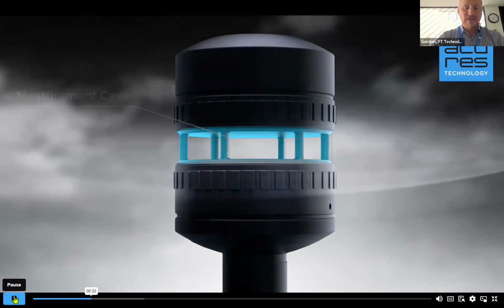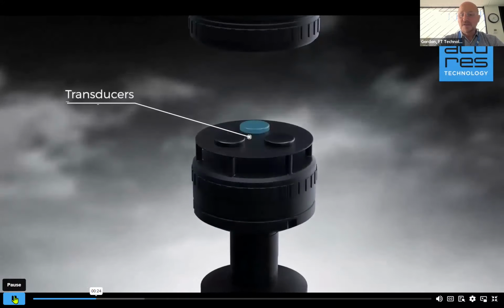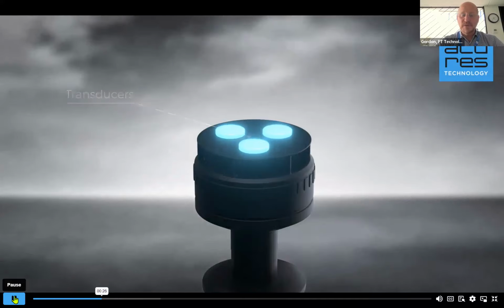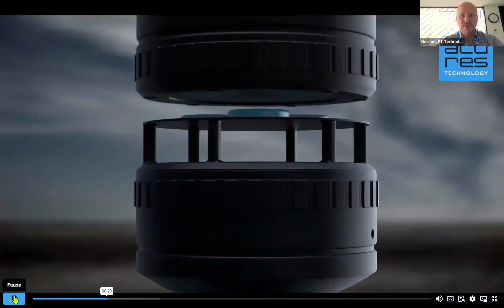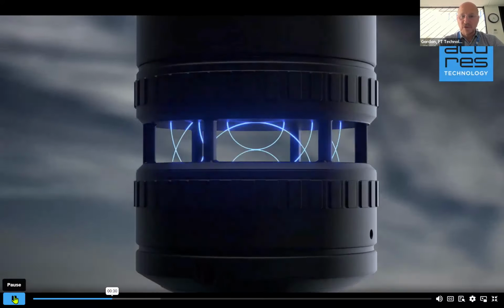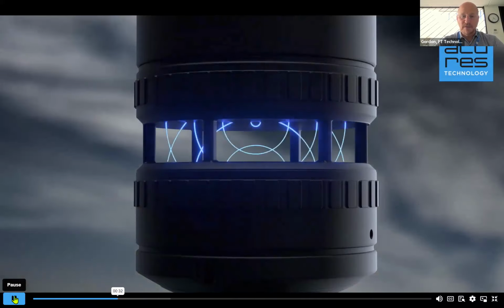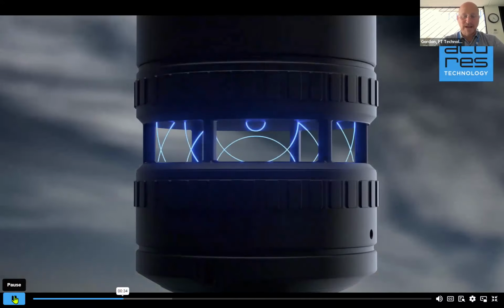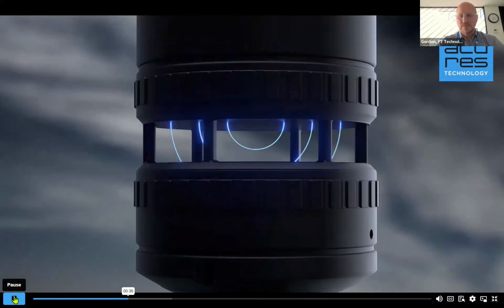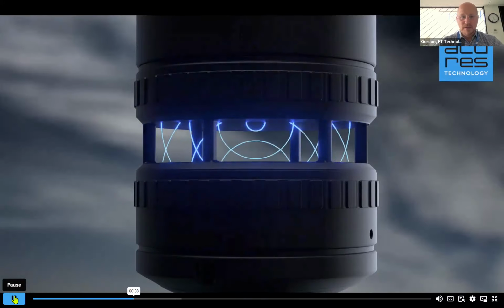You can see the measurement cavity highlighted in blue. This is a 2D sensor, not a 3D sensor, but it has a cosine response, as I mentioned. The transducers live in the top part of the sensor and provide the acoustically resonating wave into the cavity. This gives us an extremely high signal to noise ratio — a very strong signal in a small space.